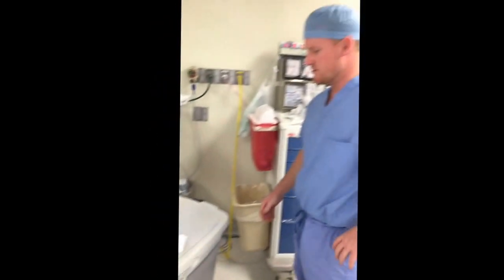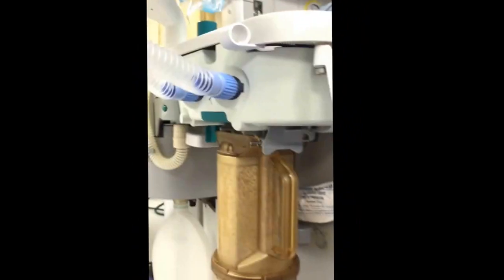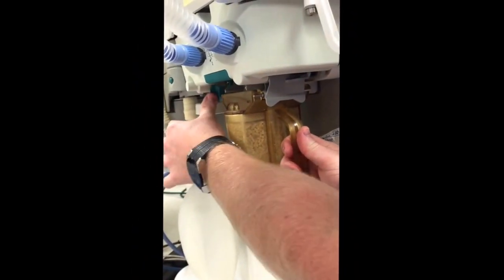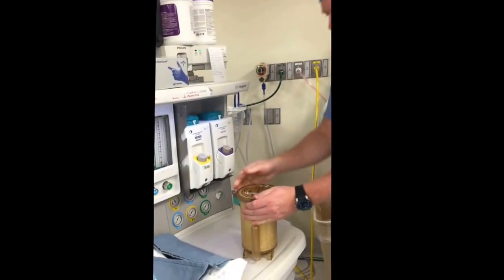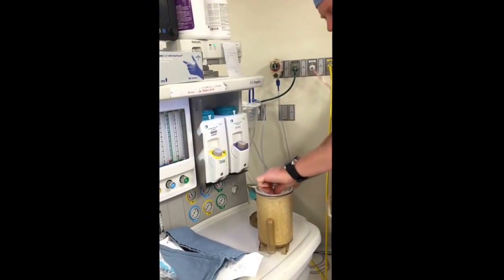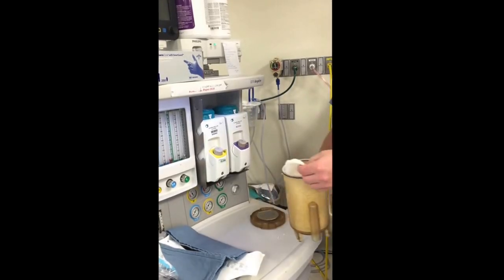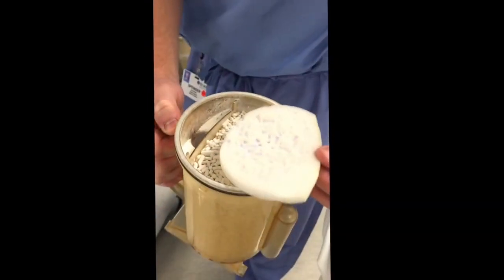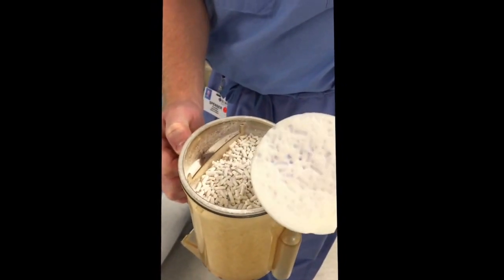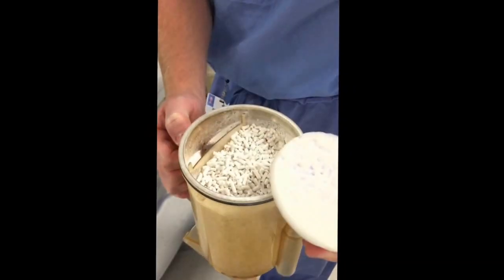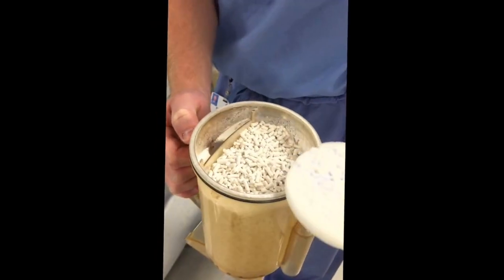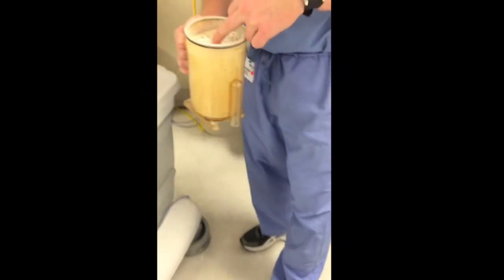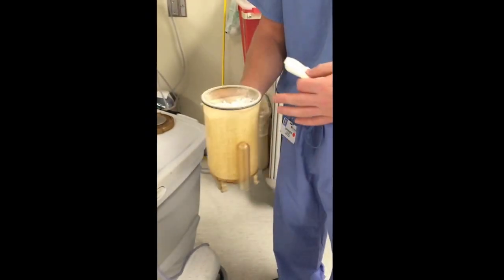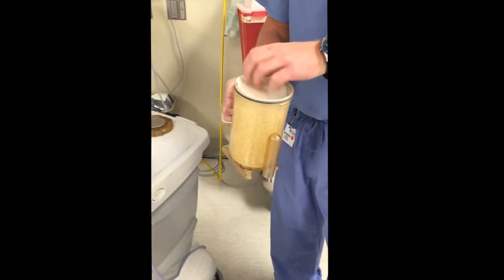So we filled our vaporizers. The next thing I like to do is check my CO2 absorbent. So unclick your CO2 absorbent on your machine. As you can see, there is some used up by the violet color. I would leave this. This seems to be still okay. I wouldn't change this. But if you would change it, you would empty it out, get new filters, and make sure you shake it to reduce the chance of channeling.